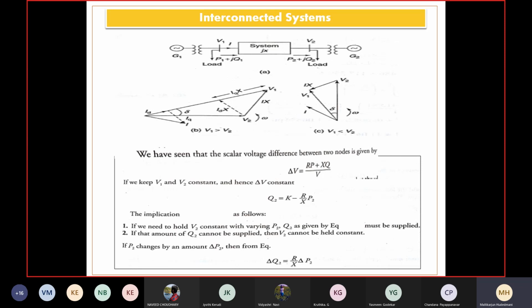Then P can be varying, active power can be drawn and varied, and voltage we need to keep constant, which means reactive power has to be maintained appropriately. If we are not able to fulfill Q injections properly, it indicates that V2 you cannot maintain. So therefore, if P2 changes by an amount of delta P2, then delta Q2 is going to change by R by X into delta P2. Now there is an indirect link. P changes, it affects Q also. That's what I want to convey.